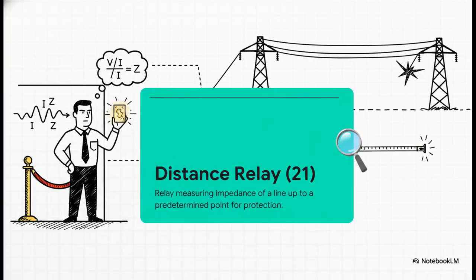So, meet our main protagonist. In the power industry, folks usually just call this the 21 relay. Think of the distance relay like a highly trained bouncer at the door of a super exclusive club, constantly checking the ID of the electricity flowing through the line. And how does it do that? Well, it relies on an incredibly simple mathematical principle. It just divides voltage by current to find the impedance.